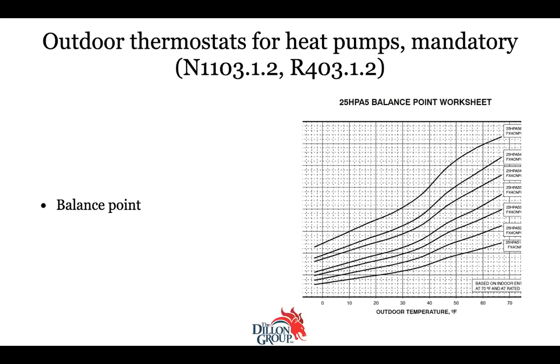And it's pretty simple. The way this works is you've got lines across the bottom. That's your degrees. And then on one side, you're going to have lines that are the load. And you basically just take a ruler, set where the load is on the vertical axis, and then where the capacity of the system is on the lines that you see there, and where those intersect, that tells you what temperature to set the outdoor thermostat at. It's not complicated. You need a ruler, you need to be able to read a chart, and you need a pen or a pencil.